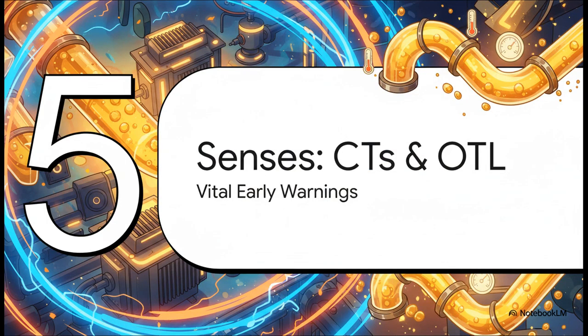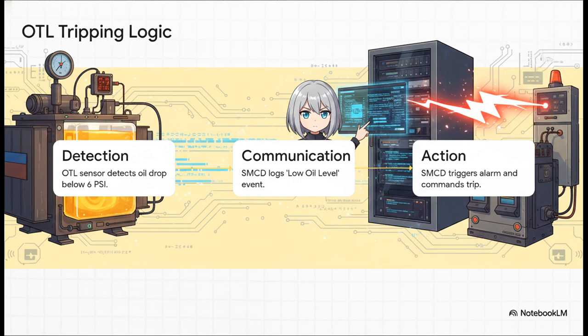Let's move to Section 5, the senses. That's the CTs and the OTL. We just talked about the CTs sensing current, but the 2026 specs actually introduced a completely new physical sense to the machine: oil monitoring. The oil temperature and level sensor, or OTL, gives the grid a vital early warning system. Let's walk through this tripping logic step by step.